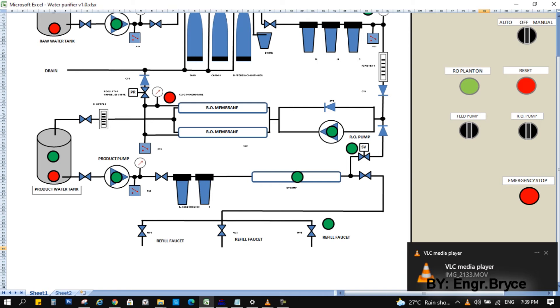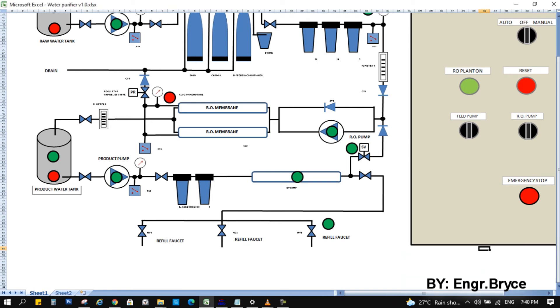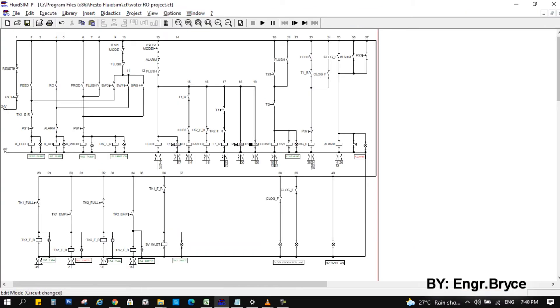For auto-flush, as soon as the automatic mode started, the timer also start counting. For this example, let's say 10 hours, or 12 hours, or 24 hours, depend on how busy is the RO plant. So after 10 hours, flushing mode executed, turning off the feed pump and the RO pump, and opening the flushing valve, and run the product pump and UV lamp, maybe for 30 seconds to 1 minute. And then repeat the cycle.